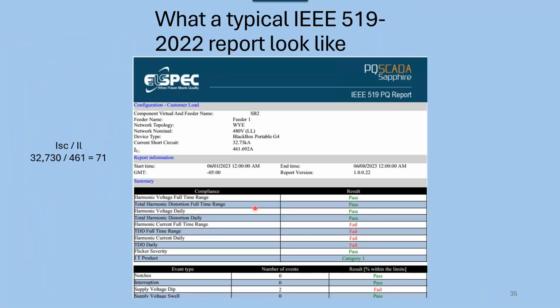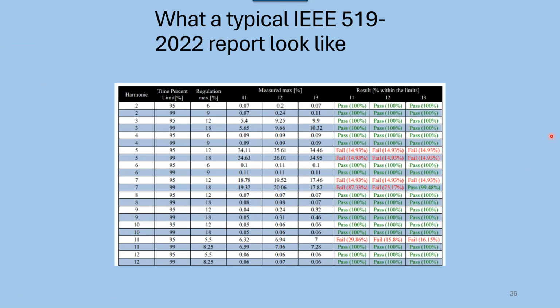Also in this report, it was interesting, my voltage daily passed and my voltage over the time range passed. So all my voltages turned out to be good. What didn't pass was my currents. So my currents didn't pass in this case. I also got some bonuses. We actually had 2 voltage dips that we recorded on the system, which I can give you on this also. So this is like a summary sheet that I put out when I generate the report for my customers. And then this is showing the actual current harmonics. Since the voltage passed, I didn't add those.